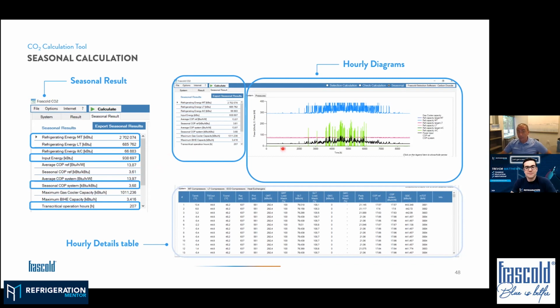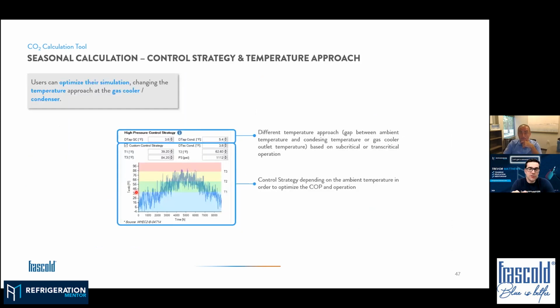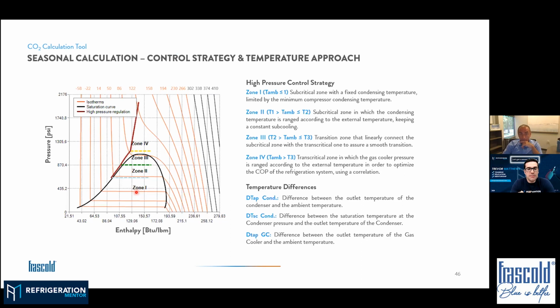So that means that the output will be on the year, on the hours of a year, how your refrigerating capacity, power consumption, and all the other parameters change. That's pretty awesome, because that's real important, especially that last slide that you were showing, the different zones, because this is something important about CO2 compared to all the other refrigerants. You don't really talk about all these different zones that you have, especially when you get up into supercritical and transcritical. And it's nice that you explained it like that, because there are different zones and your system is going to work differently. Because not only you got to worry about when it's really, really hot out, when you're in supercritical or transcritical, you got to worry about when it's really, really cold out as well to keep that system up and running, because those compressors will shut off. Correct. Awesome. So that's pretty cool about this seasonal calculator.